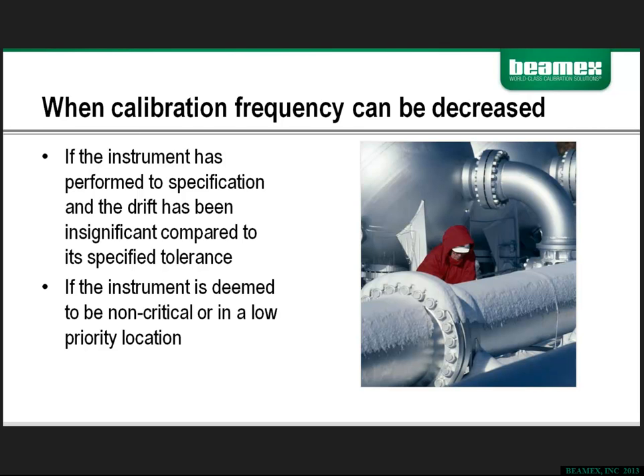When can calibration frequency be decreased, meaning when can I adjust the calibration interval to make it a longer period of time between calibrations? If the instrument performs within manufacturer specs over an established calibration interval with little or no drift, and then based on the location, is that instrument in a critical area? Is it in a low priority location? These are things that would have to be determined, either by the individual or by your particular regulations that govern that process. So the calibration interval may be increased, thus reducing calibration frequency. There's a rule of thumb in calibration that if you can go 3 successive calibration cycles with no out of tolerance conditions reported, that would typically justify an increase of 50% of that calibration interval.